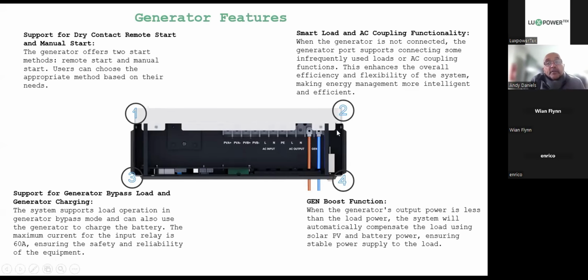And number 2, you cannot enable load with the generator connected here. You will send your generator to the scrap heap in a very short space of time. So don't do that. Be very careful, because it's going to push power up here. So this enhances the overall efficiency and flexibility of the system, making energy management more intelligent and more efficient. And then point number 3, we can support generator bypass load and generator charging.